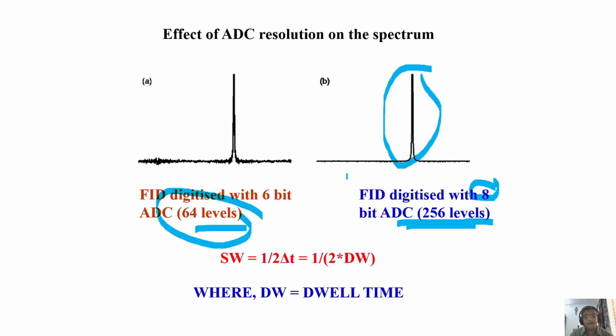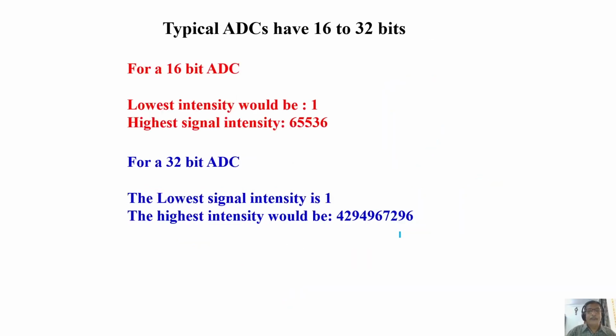And of course, this ADC resolution is also important for spectral resolution. I told you, the spectral width, I gave the expression 1 over 2 times delta t, where delta t is the dwell time. So the dwell time has to become smaller and smaller so that you can digitize with more number of points. Remember the Nyquist theorem, everything I discussed, where this is the dwell time. So higher digitization points is better for us. So a higher bit ADC is always good to utilize. Okay. A typical ADC can have 16 to 32 bits normally. Of course, in NMR, we use a 32-bit ADC. In some older spectrometers, a couple of decades old, people are using a 16-bit ADC.